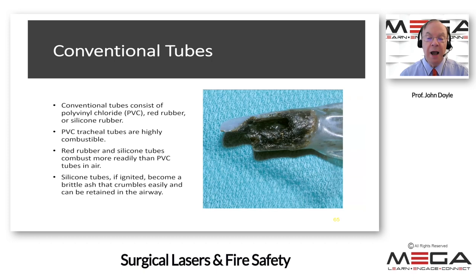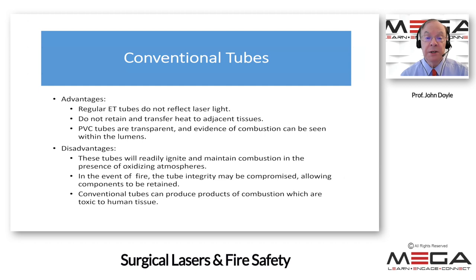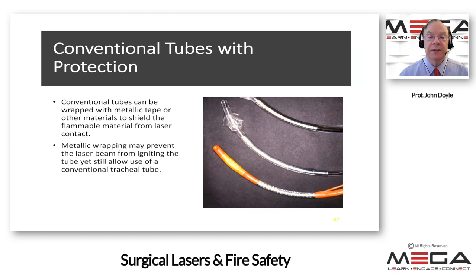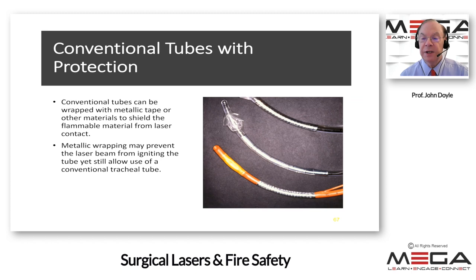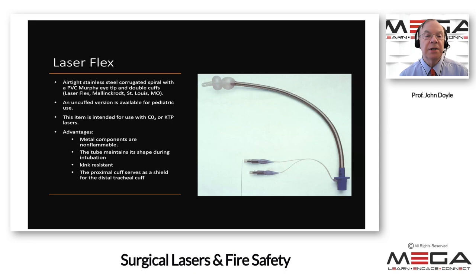With intubation, ventilation can be monitored and controlled, and both IV and inhalation agents can be used — but the endotracheal tube could catch fire if a conventional tube is used. Conventional polyvinyl chloride or silicone tubes are highly combustible, particularly in oxygen-enriched environments, and can produce toxic products of combustion. Some people protect a conventional tube with metal wrap, which may prevent the laser from igniting the tube. However, in current practice special custom tubes have largely replaced this approach.